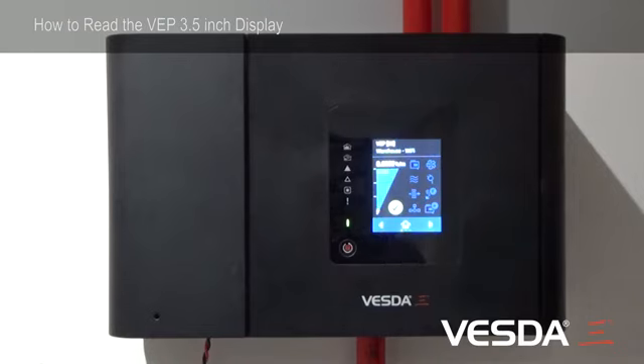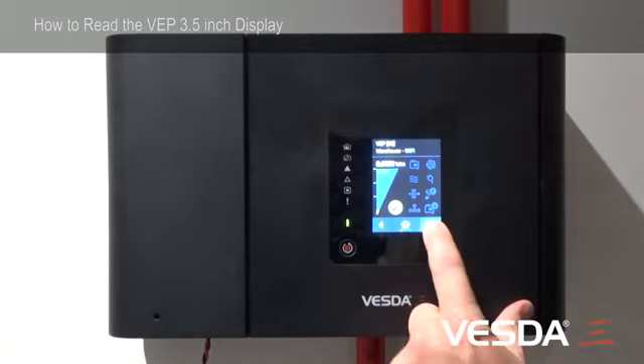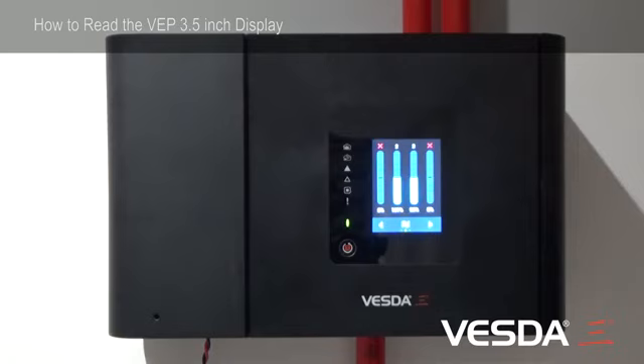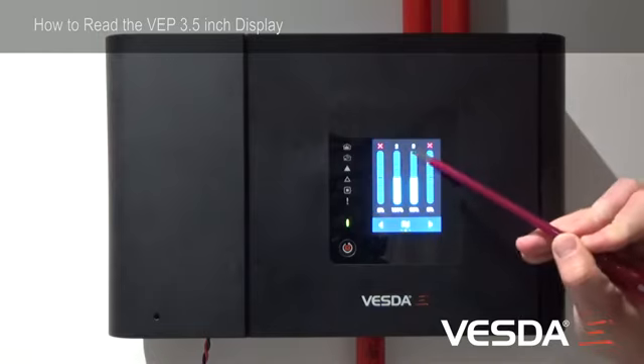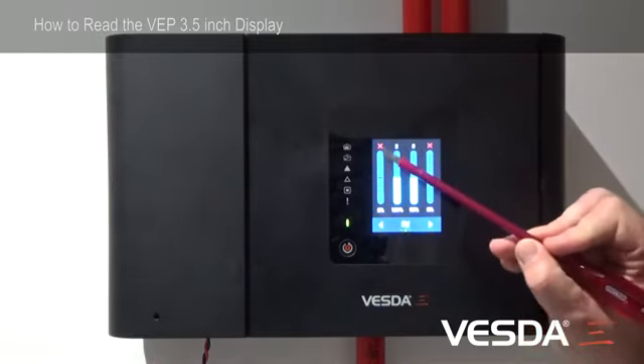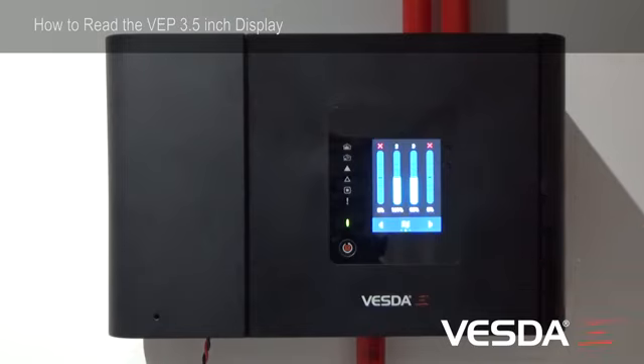Moving over to the next screen, you're also able to have a look at the airflow indication screen. You can see from the detector that there are 2 pipes enabled, pipe 2 and pipe 3. Pipe number 1 and 4 has been disabled in the program, and presently we're indicating 101% and 99% of normalised flow.